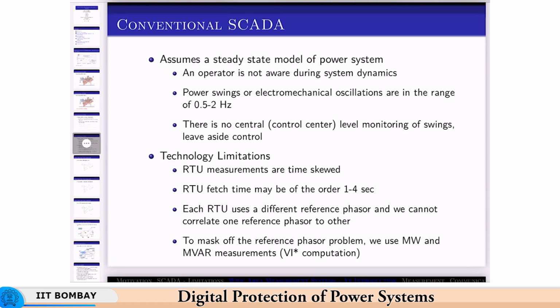Also, because they don't have a common timestamp, each RTU has its own reference phasor, and that is why we cannot correlate one phasor to another. So even though we may have the voltage of two substations, as seen in an earlier slide, we may not be able to compare the phasors because the reference phasor is not common.